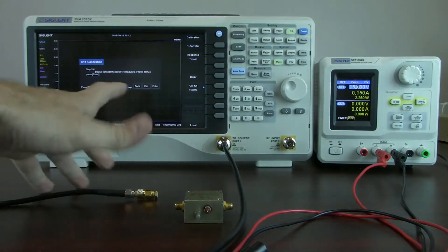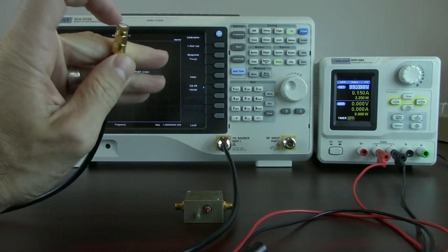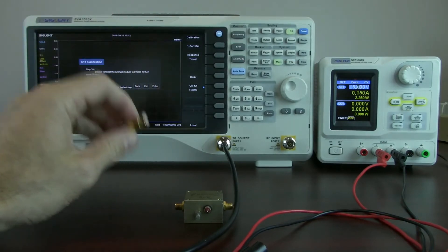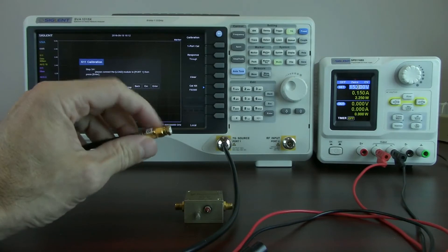This calibration process is going to remove the effects of the attenuator and the cabling, or at least minimize them. In this particular case, we don't have a fully characterized set of shorts and loads, so it is going to have some error, but it is going to be better than if we were to not perform that calibration.